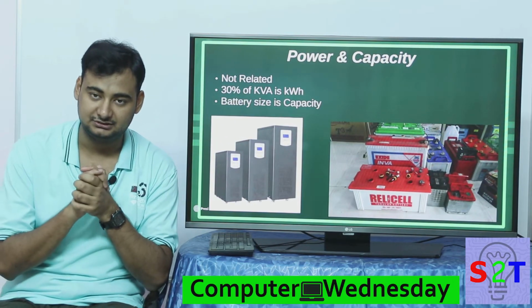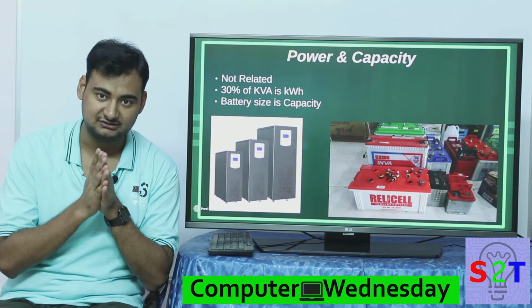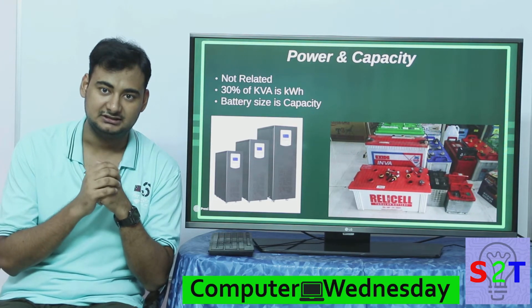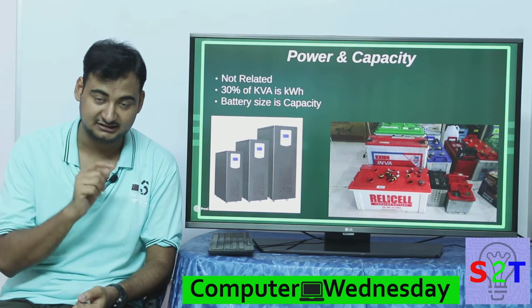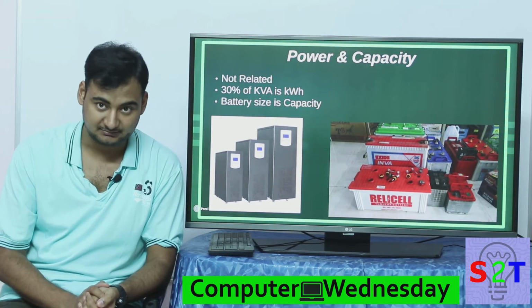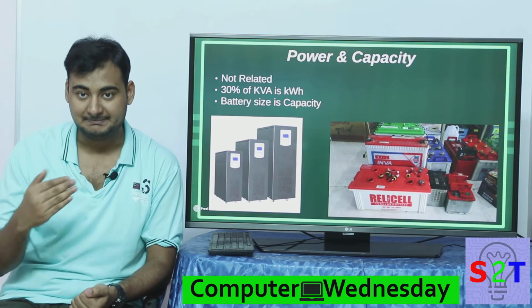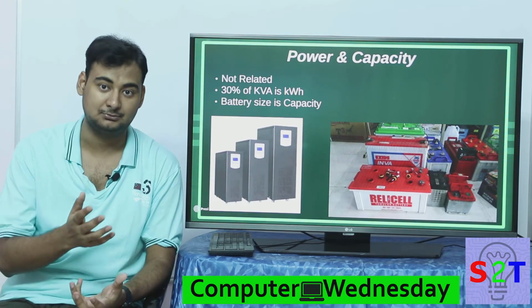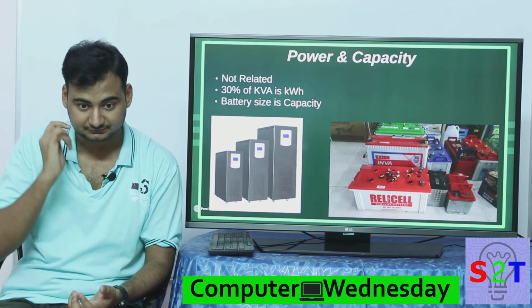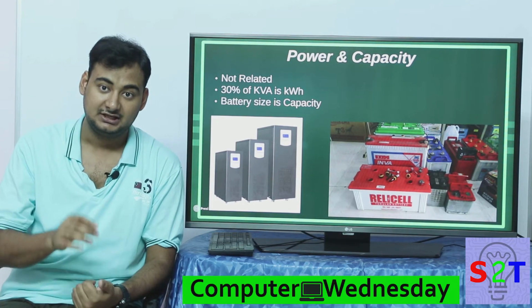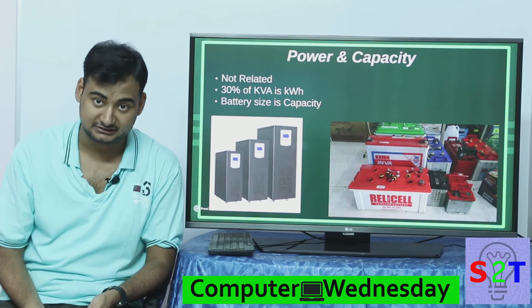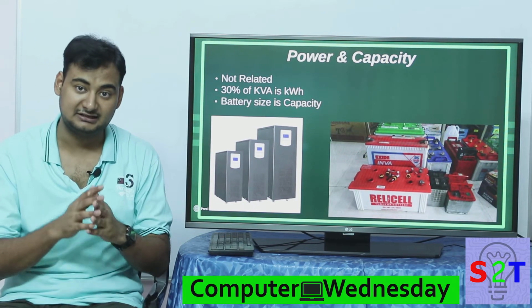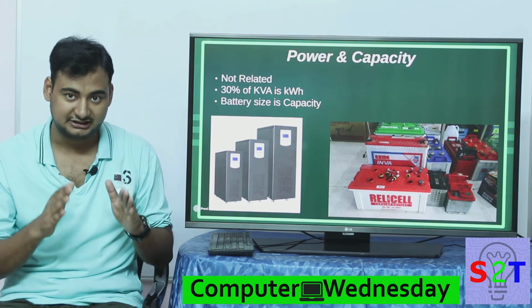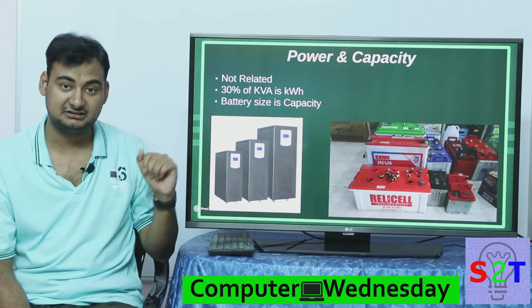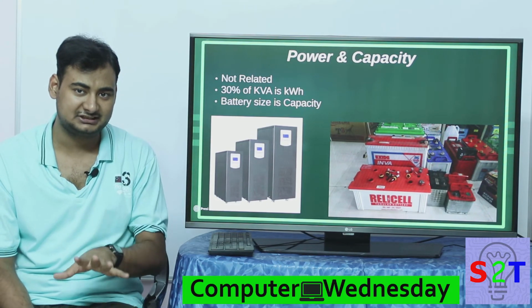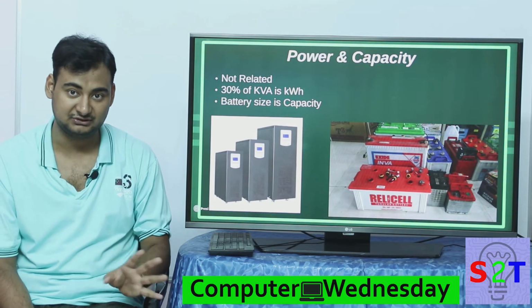So one thing I want you guys to take away from this is that power and capacity of this sort of thing are completely independent. Second, the reason why all UPSs are rated in kVA rather than kilowatt-hour or amp-hour is very simple. kVA is independent of power factor. Depending on the load, each object, like let's say a jet pump or a tube light, even though they could be rated for the same wattage, will have different power factors. Based on those power factors, their power consumption actually varies a lot. So that's why they generally use kVA, and also kVA is generally bigger than kilowatt. So 30% lower is a very good idea. It's a safe bet. Let's say you get a 10 kVA UPS, only put 8 kilowatt of load on it. Don't put a 10 kilowatt load, you will fry the UPS.